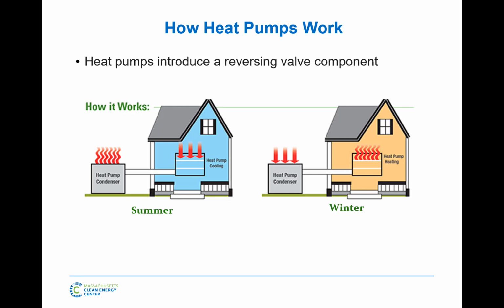Now, somebody might say, what if it gets to 0 degrees? There's no heat left at 0 degrees. Well, unless you're at absolute 0 temperature, there is heat in the air. So 0 degrees might be cold for us as humans, especially when it's really windy and snowy and all sorts of fun stuff in the air. But for the refrigerants that we use in here, 0 degrees is just another location on the pressure enthalpy diagram. It has a little less heat, but it's still got plenty of heat. We'll talk about that later and how it affects efficiency and capacity.